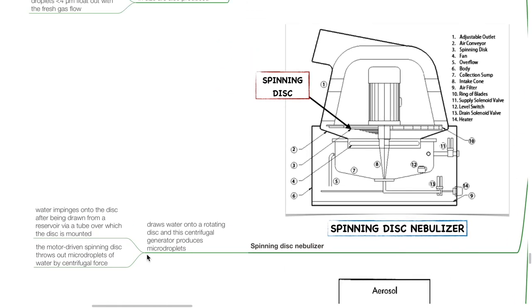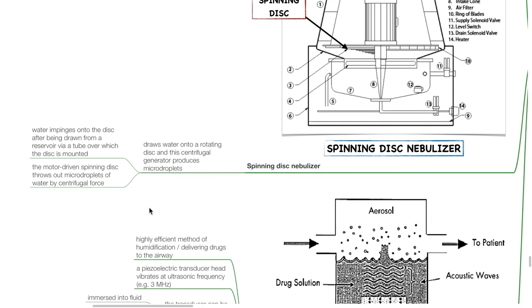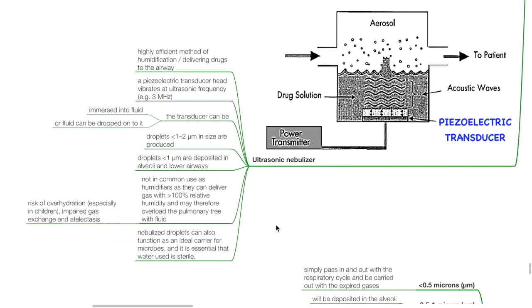The spinning disc nebulizer draws water onto a rotating disc and centrifugal force produces micro-droplets. The ultrasonic nebulizer is a highly efficient method of humidification and drug delivery; a piezoelectric transducer head vibrates at ultrasonic frequency, and droplets of less than 1–2 microns in size are produced. Droplets of less than 1 micron are deposited in the alveoli and lower airways. The ultrasonic nebulizer is not commonly used as it can deliver gas with more than 100% relative humidity, potentially causing overload of the pulmonary tree with fluid, impairing gas exchange and causing atelectasis. Nebulized droplets can also function as carriers for microbes, so the water used must be sterile.